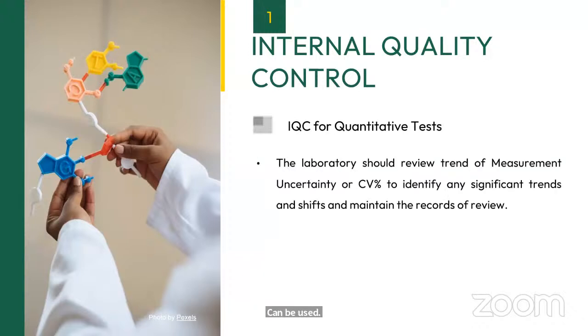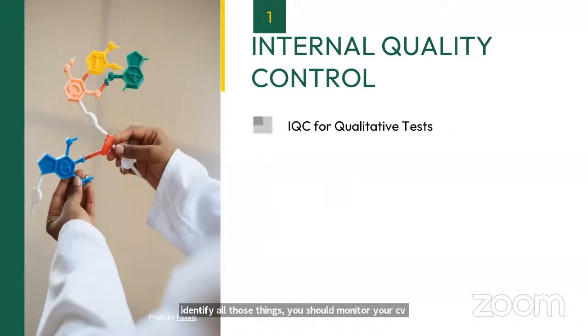The laboratory should review trends of measurement uncertainty or CV percentage to identify any significant trends and shifts, and maintain the record of review. So measurement uncertainty or CV percentage should be periodically monitored and documented, and reviewed for trend or shift, whether the CV percentage is increasing or decreasing. If it is increasing, that means your precision is worsening and your examination method is no more stable. So to identify all those things, you should monitor your CV percentage and measurement uncertainty on a periodic basis.